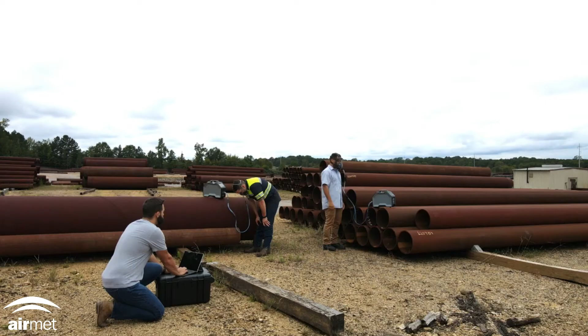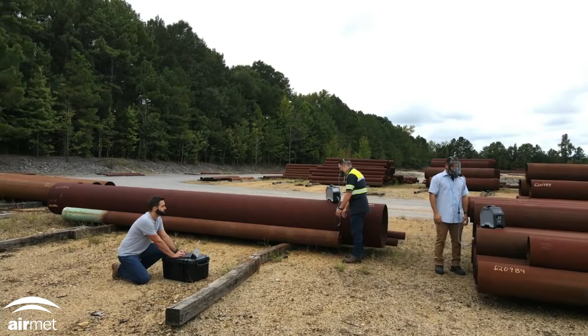With the QuantiFit 2, we've completely removed that. With battery power, you now can unplug from mains power and do fit testing in any environment, inside in very clean indoor air quality or outside in any environment that you'd like, as long as air is present. And that's only achievable with controlled negative pressure. So no more candles, no more creating environments to do your fit testing.